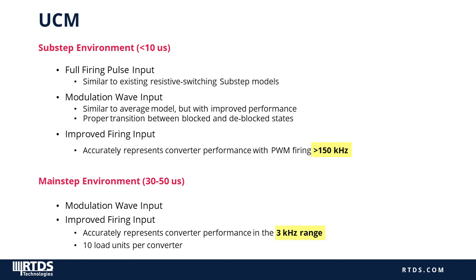Improved firing has a substantial effect on the UCM's performance. In the sub-step environment, we can model very high switching frequencies — over 150 kHz — without needing to drive the time step into the nanoseconds range. This means we get accurate representation of a great frequency range while remaining conscious of the computational burden and simulation hardware required. Even more impressively, improved firing means that for the first time, we can run converters in the main time step — say 30 microseconds — while still achieving full switching detail in the 2 to 3 kHz range, implying huge savings in simulation hardware requirements.